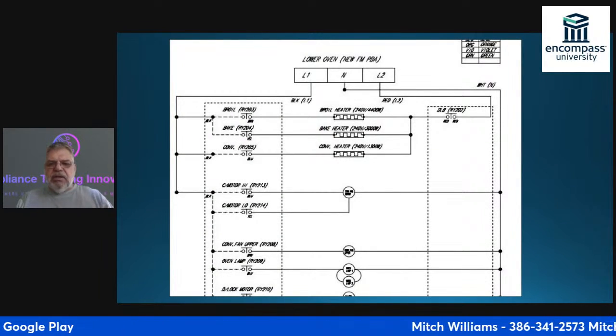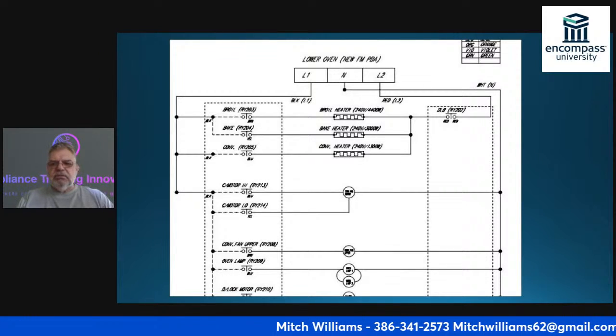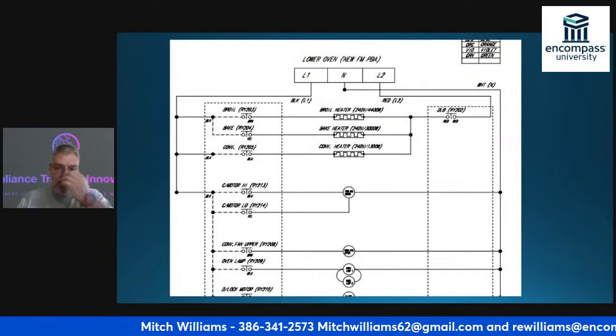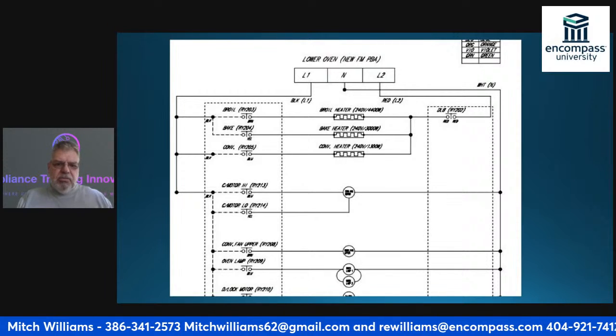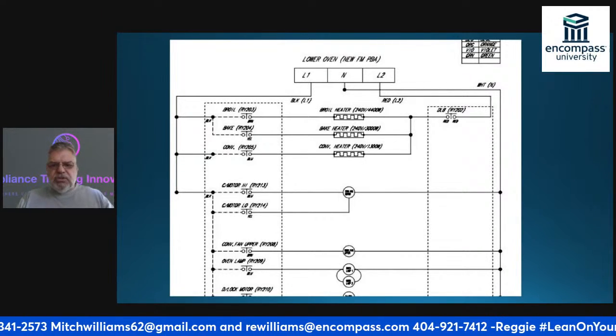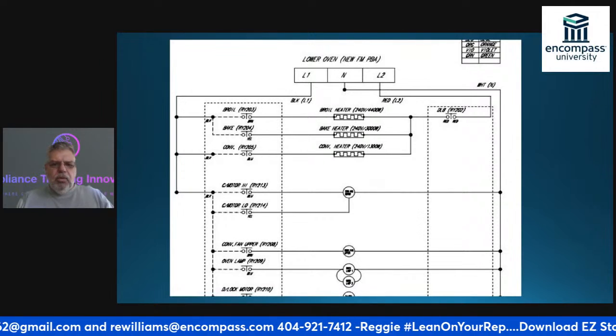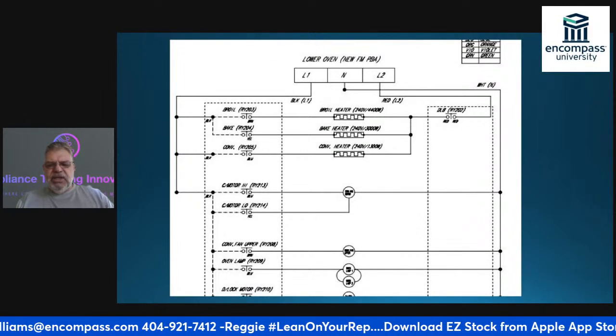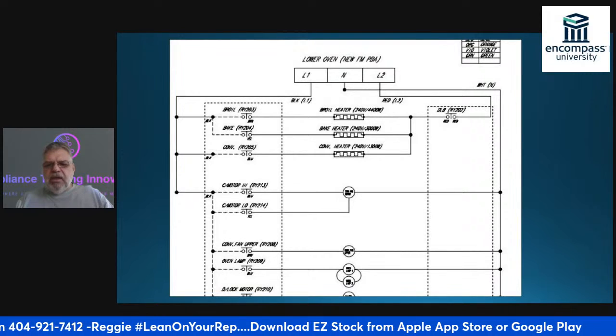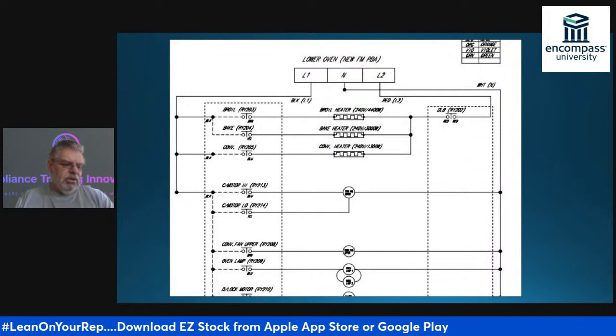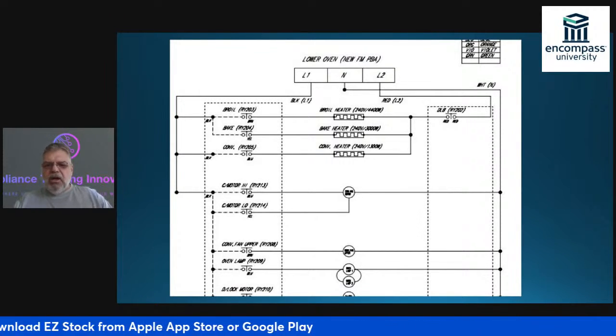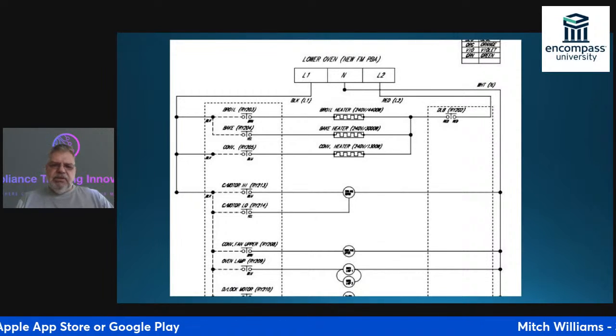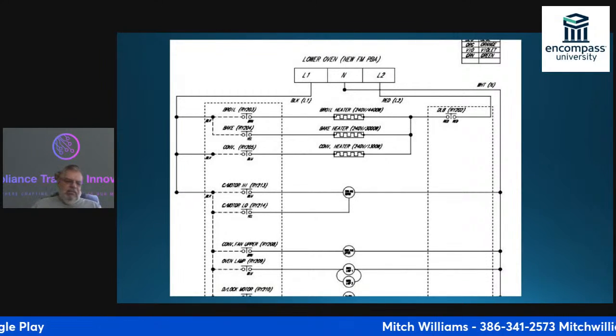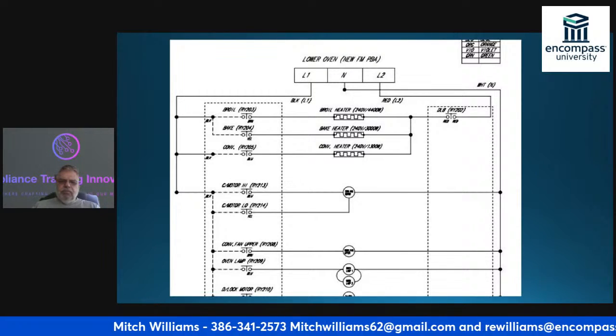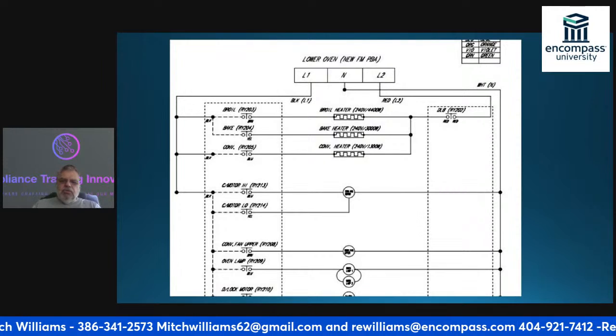Okay, so here is the lower oven schematic. You can see you have your bake, broil, and convection switches. Those all go through the L1 side, and then you pick up the L2 side as long as the high limit is closed. What I'm telling you is, if I have a blown high limit switch, I'm only going to get 110 volts. There is no neutral, it's only an L2.